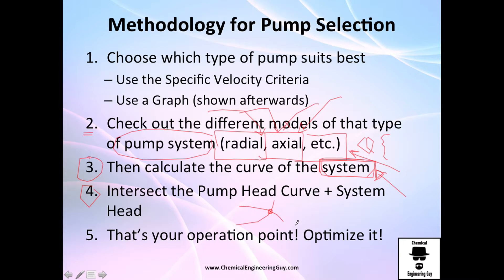Once you have that point, it's time to optimize it. For example, closing a gate valve can shift the system curve and give you better efficiency and lower power requirements. Finally, once you have your final operation point, get approval, buy the pump, install it, do some tests, and start operating.